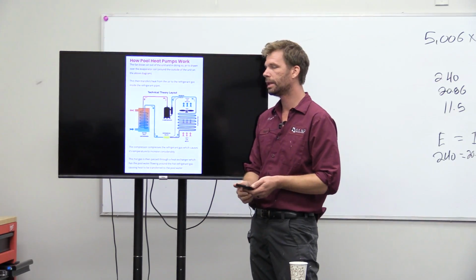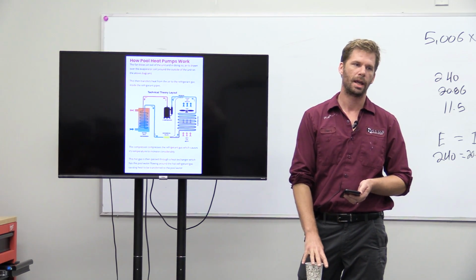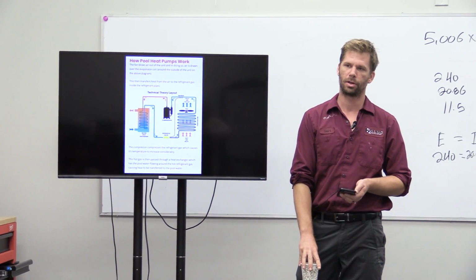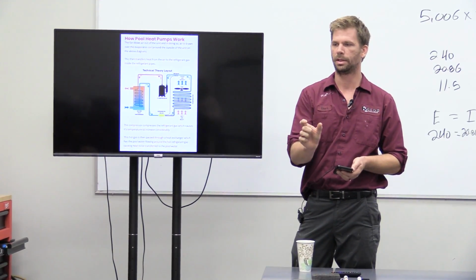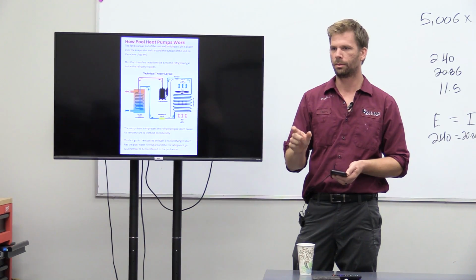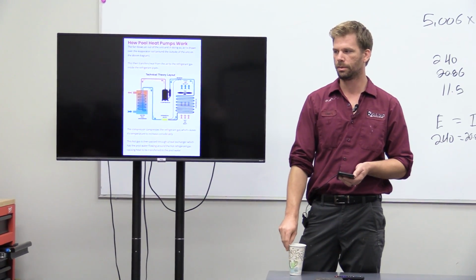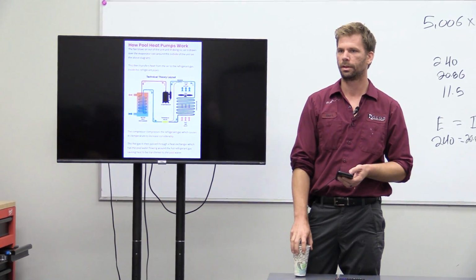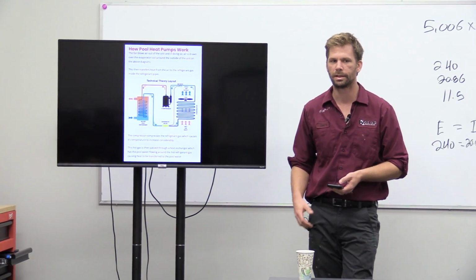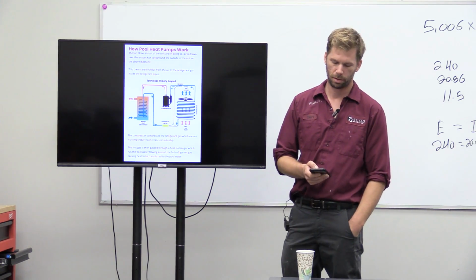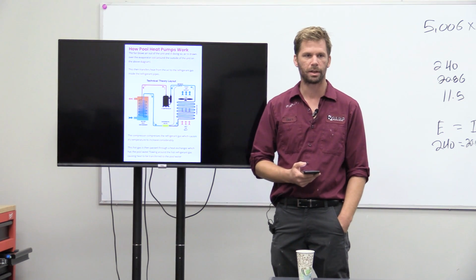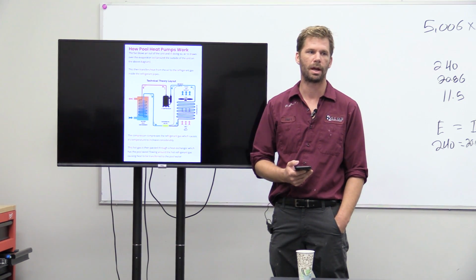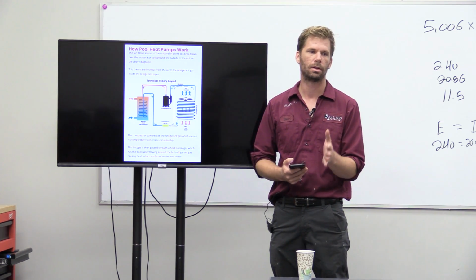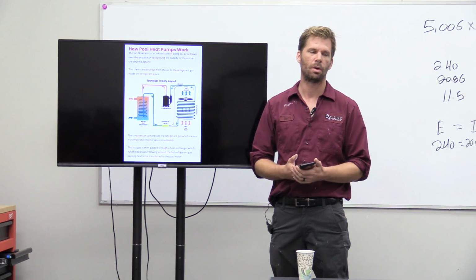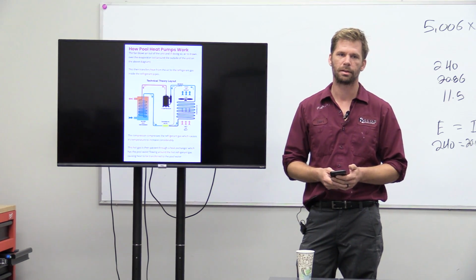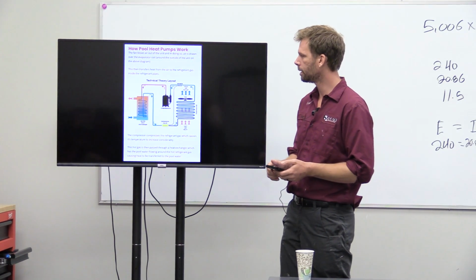Pool heater TXV replacement is one of your most common projects on there, and they can be tricky. They're a lot larger, and the connection points are really close to the TXV. You got to keep it safe. But if you're ever quoting a project with refrigerant on your pool heaters, just a side note, your liquid line dryer is a 1/2 inch. It's not 3/8, not your typical liquid line size. The liquid line is larger, it's a 1/2 inch. So whoever is ordering parts needs to know, like you tell Tim or whoever, also order a 1/2 inch liquid line dryer for this project, because we don't always have one just sitting at our shop. They're kind of an odd size. So just keep that in mind. That's off topic, but keep that in mind.